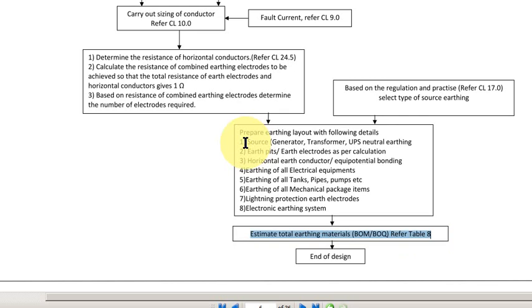The layout - I have already explained two typical layouts previously. You have to show all the source earthing: generator, transformer, UPS neutral. You have to show the earth-pits, earth electrodes. You have to show the horizontal conductors along with the conductor size.